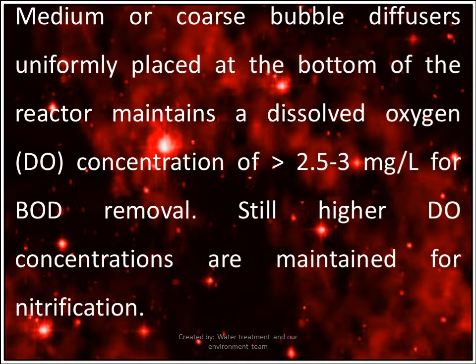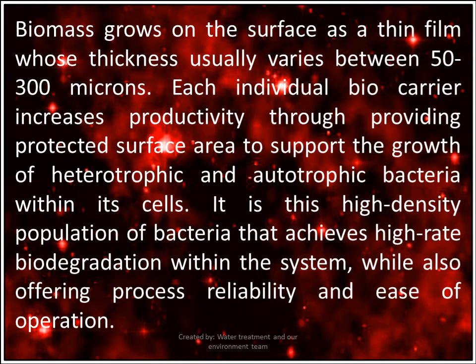Medium or coarse bubble diffusers uniformly placed at the bottom of the reactor maintain a dissolved oxygen concentration greater than 2.5 to 3 ppm for BOD removal. Still higher DO concentrations are maintained for nitrification. Biomass grows on the surface as a thin film whose thickness usually varies between 50 to 300 microns.